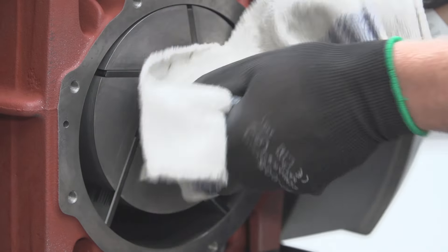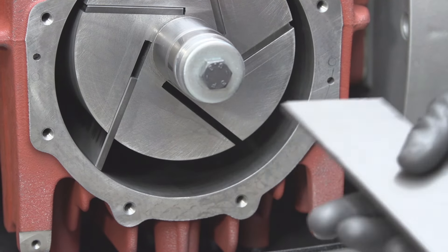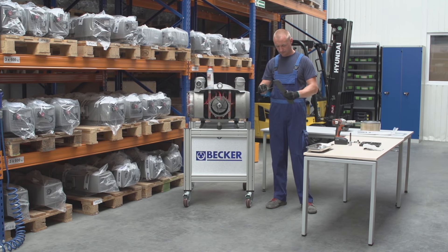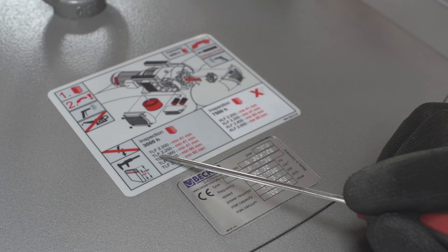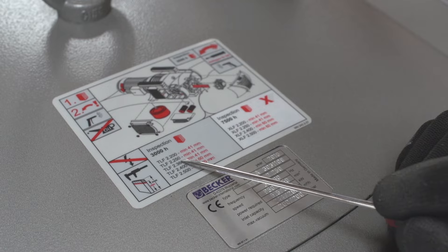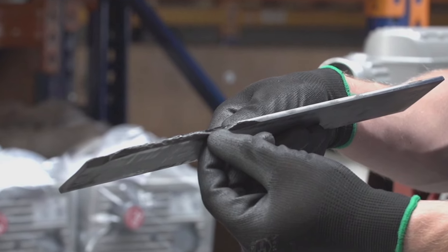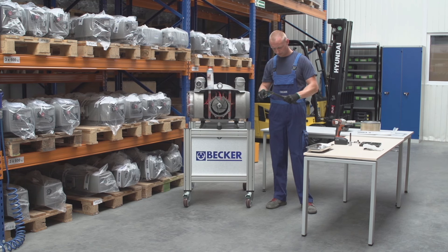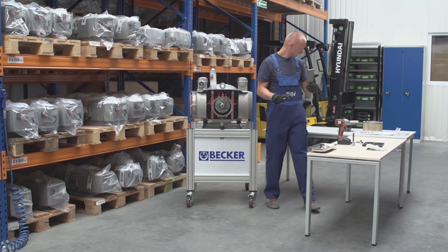Thoroughly clean the pins and rotor shaft to avoid any contaminants from getting into the cylinder, which can damage the vanes. Using a caliper, measure the height of the vanes and compare it to the Becker recommended minimum height. This information can be found on the maintenance label directly on the pump housing or in the technical specifications on the Becker website. Check each vane for chipped edges or cupping on the flat side of the vane. If the height of the vane is near or below the recommended dimension or has signs of excessive wear, the vane needs to be replaced.